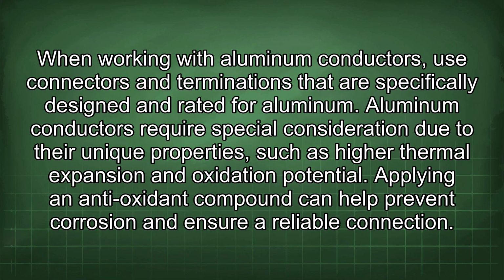When working with aluminum conductors, use connectors and terminations that are specifically designed and rated for aluminum. Aluminum conductors require special consideration due to their unique properties such as higher thermal expansion and oxidation potential. Applying an antioxidant compound can help prevent corrosion and ensure a reliable connection.